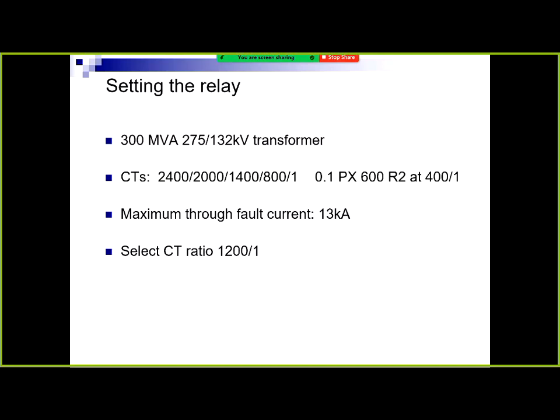But P class are very common for people connecting to our network, we see. Even high voltage feeders, 132 kV feeders, we see. They build the feeder and put a set of CTs down the other end. They've got two PX for us, for the feeder protection, and P class for their own protection. Nothing wrong with P class, but prefer PX.